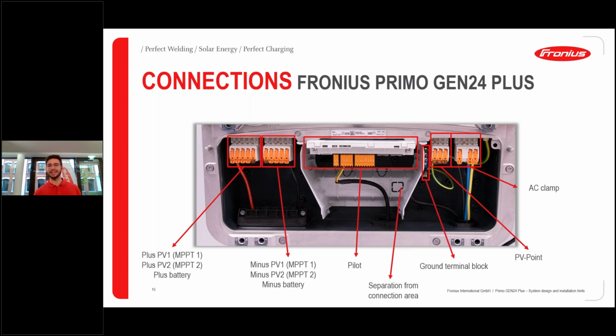In the middle, we can see the data communication. This is more or less the brain of the inverter and also the communication center. So it's called the Pilot, and it's standard integrated. So there is no way that you get a light version like you could with the snap inverter. It's really not functioning without this. So it's standard integrated, and it is the communication center. This whole Pilot, this communication center, is covered with this separation from the connection area to just protect it from DC and AC voltages that may damage this product.